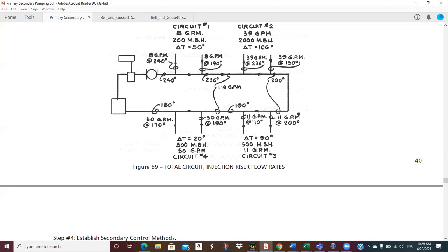So, the final. Now Nick, keep me straight. Final on Monday at 10:30 to 12:30, and it'll be over VRF. Thank you, Nick, I left that off the list. It covers air control, control valve sizing, and primary-secondary up to this point. I will not include one pipe primary. It could be somewhat short, because I probably will ask you to calculate some CVs. So Q is equal to 500 times GPM times delta T. I don't consider that to be over the top.